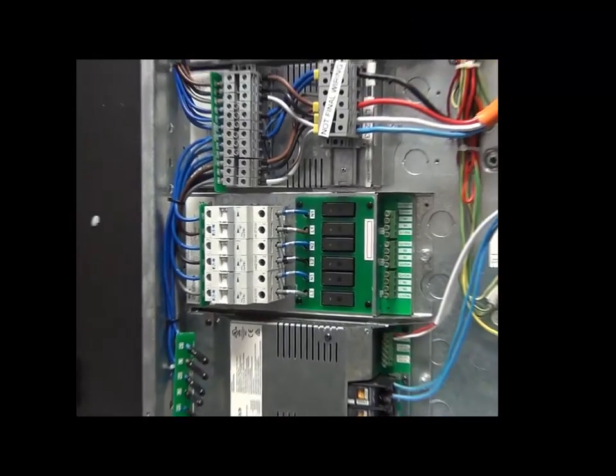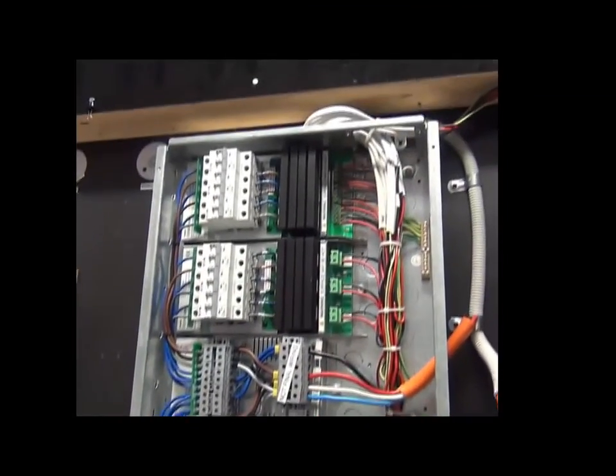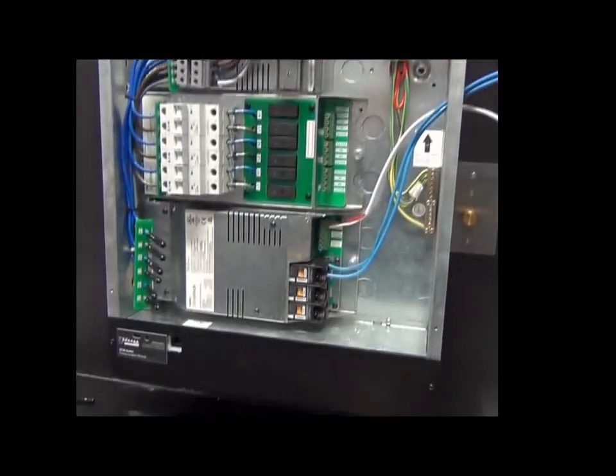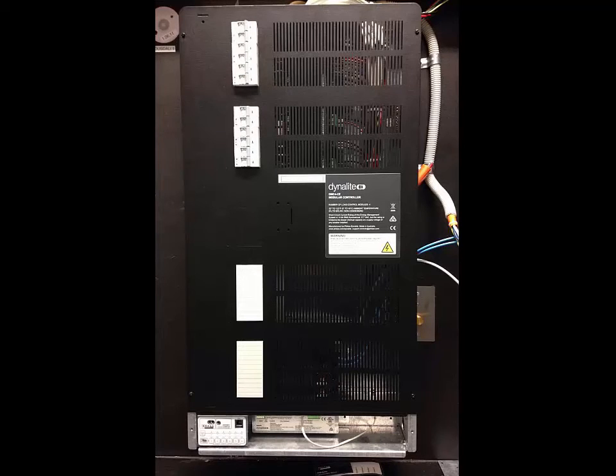This device should be de-energized before terminating the control and data cables or disconnecting the comms module. Do not leave the front cover off for any length of time after the installation. Excessive dust can interfere with cooling.